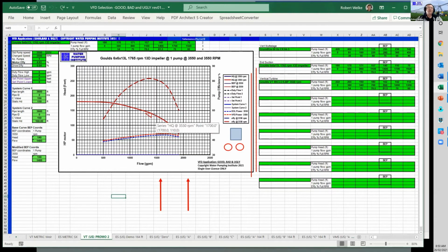When the pump is running at full speed, the power drawn is actually higher by about 5 or 6%. But as we slow the motor down, let's throw that back to 3000 RPM, you can see all of those lines separate, and you can see a very specific trend. This triangle represents the best efficiency point on the pump, and it moves down and to the left quite significantly. Therein lies the issue with VFD application: tracking where that best efficiency point goes.